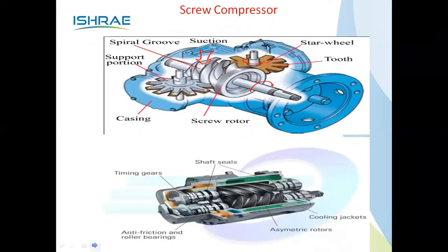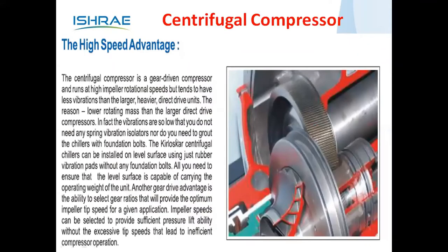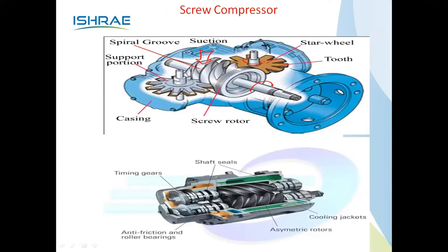The screw compressor — there is also a single screw compressor technology where the screw rotates between two star wheels, creating the compression effect. The single screw compressor is more effective than the double screw compressor. Single screw compressors are now more commonly used compared to twin screw compressors, which consume more power and are less efficient.